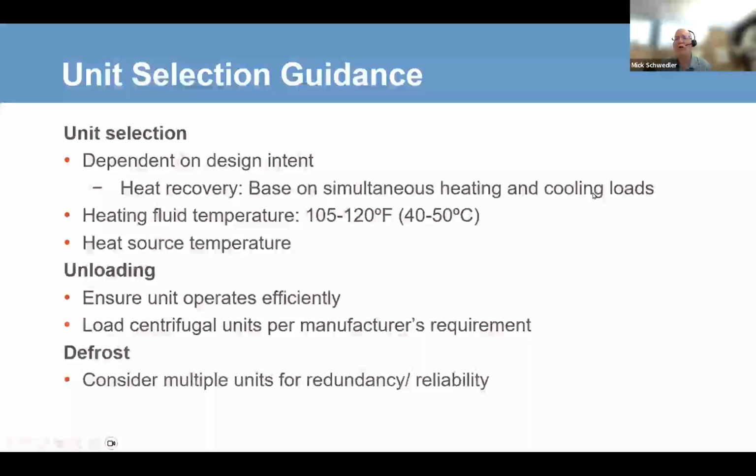We'll talk a little bit more about defrost, but often, let's say it's 25 degrees outside and we're extracting heat from the 25-degree air. A lot of times when it's 25 degrees, at least where we live in Wisconsin, it can be pretty humid. When you get to higher elevations, it's not as humid. But as we extract heat from that outdoor air, the air temperature leaving that outdoor unit is colder. And if it goes below the outdoor air dew point, water forms. And if it's below 32 degrees Fahrenheit, frost and ice can form.